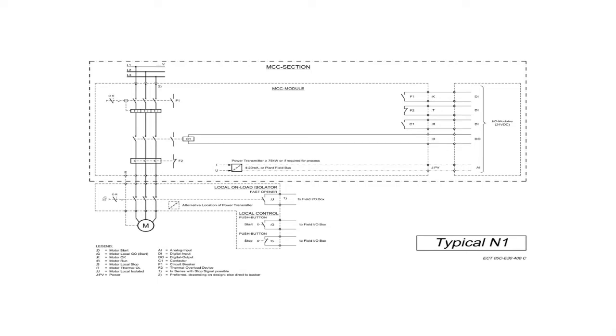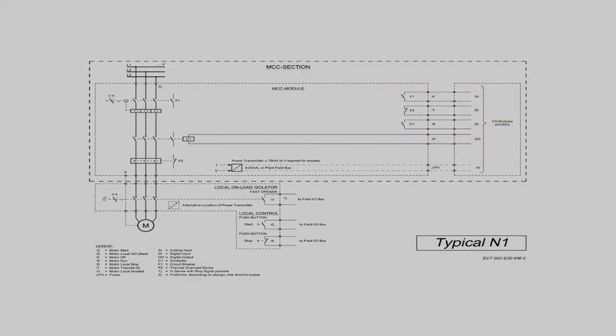On the left side, we can see the main circuit, where we have installed a few main components like switches, protection devices, and contactors. When we go down on the left side, we see the motor, and just in front of the motor, we are installing the local on-load isolator switch. You can see it's marked with a dashed line around the local on-load isolator. And here we also have some control devices like local push buttons for start and stop. On the right side of this picture, we can see the control circuit. Now we know how it's installed in the network.